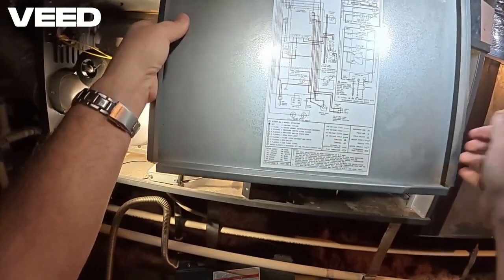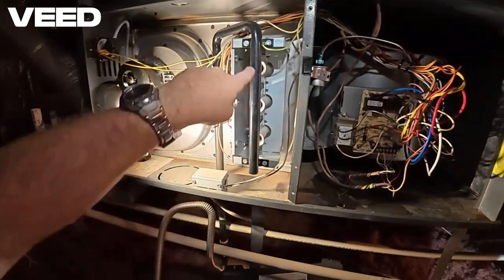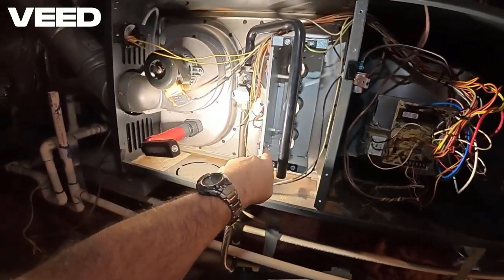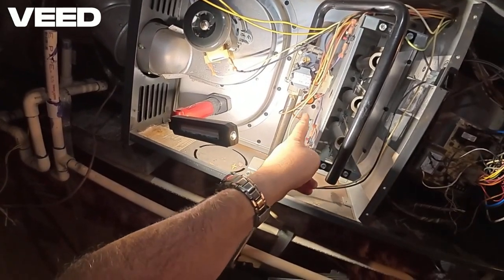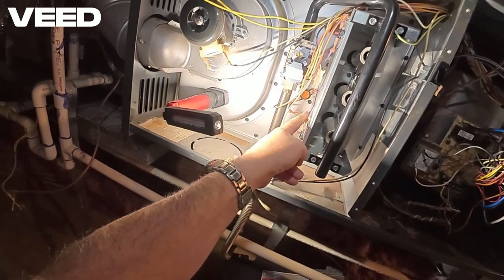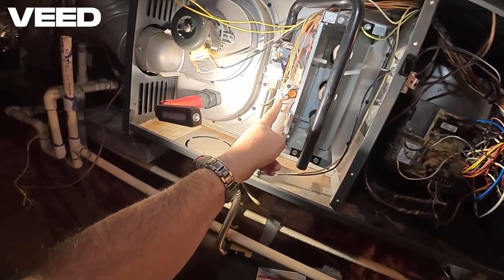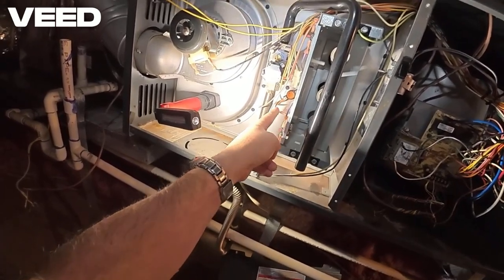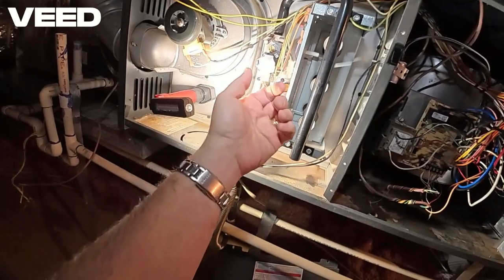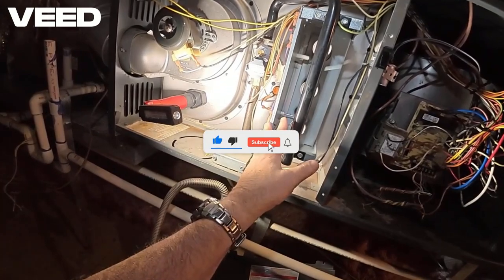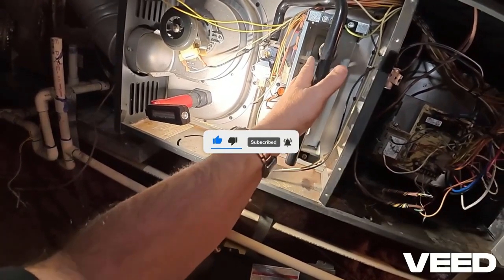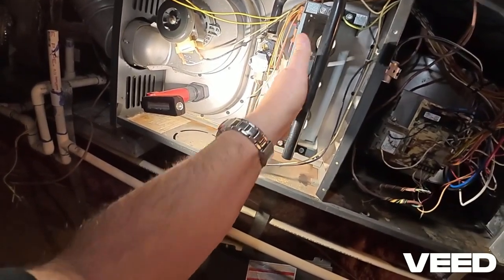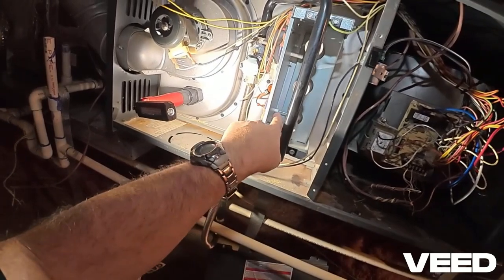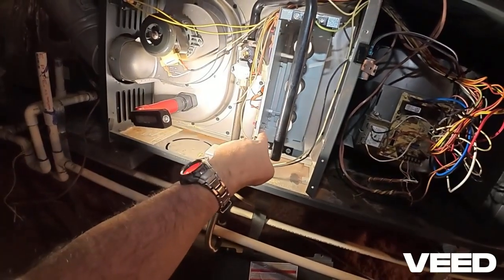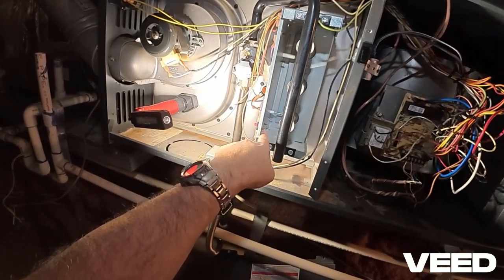6 flashes is open rollout. So rollout switches, there's one here and there's one down here. And these, again, are also wired, and they will open, and as well, it's a safety. So when flame comes back into this assembly, this burner assembly, or there's too much heat in here, and again, it's often coming back, these will trip, and they're called rollout switches again.